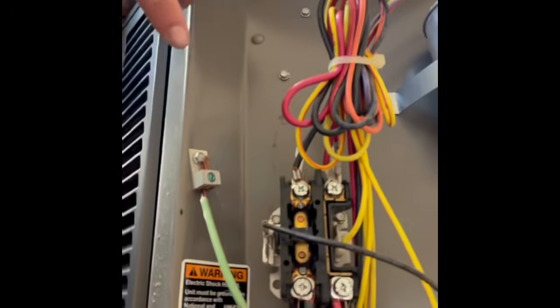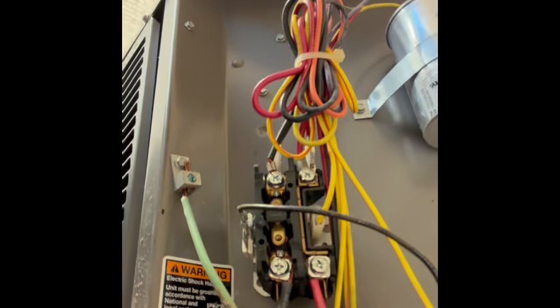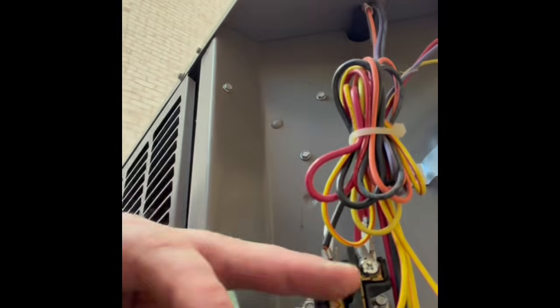All right, now that we've got the condenser open and the electrical panel, we're going to look at the internal portions of the electrical system, such as the contactor, or you could call it your high voltage distribution system. That's where your high voltage comes into the system. And I'll show you here. So your high voltage is coming in right through here on these 2 legs. This is where your low voltage comes in, coming from your thermostat.